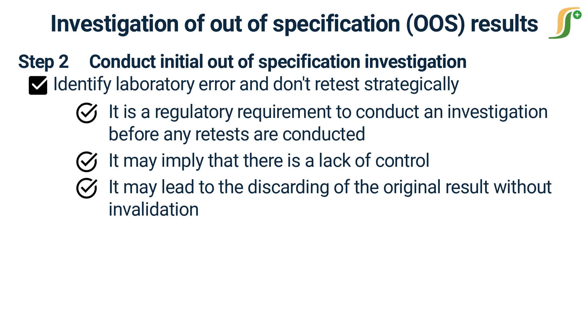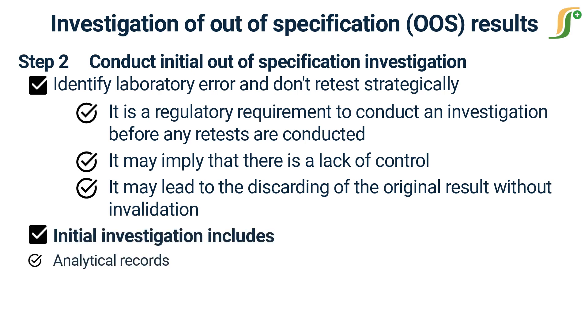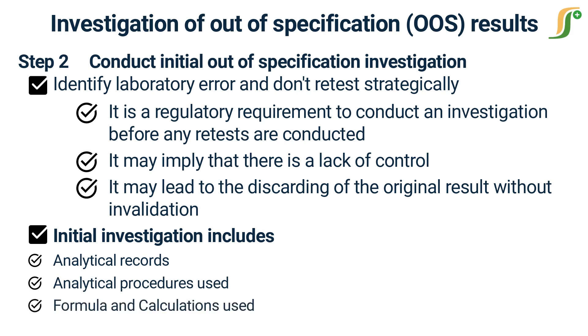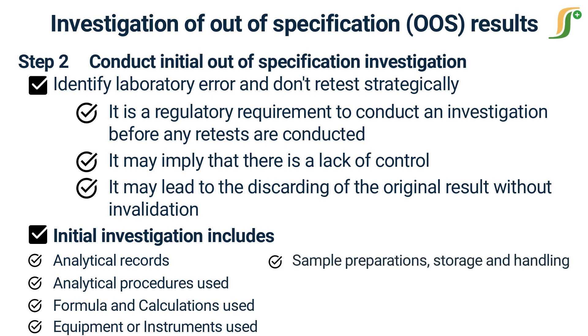This should be done by a combination of standard operating procedures supported by an OOS investigation form. This approach minimizes errors and subjective decisions and ensures the investigation is thorough and fully documented. The initial investigation includes but is not limited to examination of analytical records, raw data, laboratory notebooks, analytical procedures used, formula and calculations used, equipment or instruments used, sample preparations, storage and handling, testing environment, and analyst error.